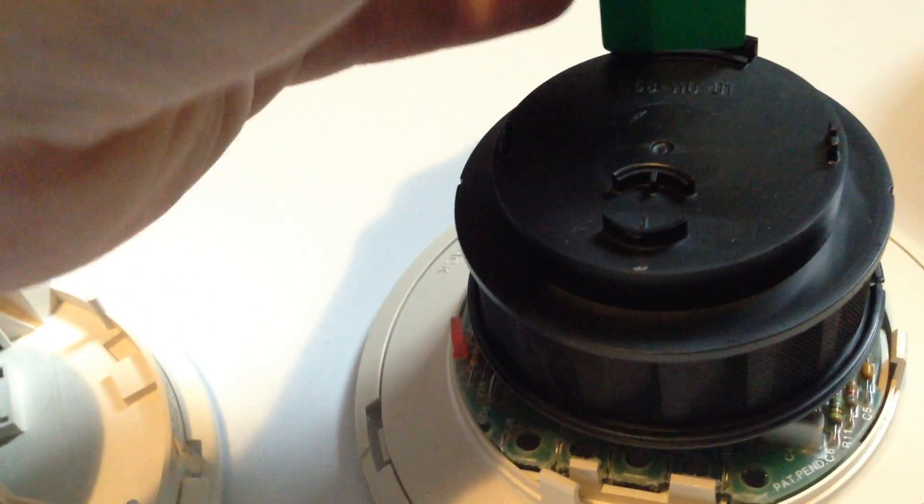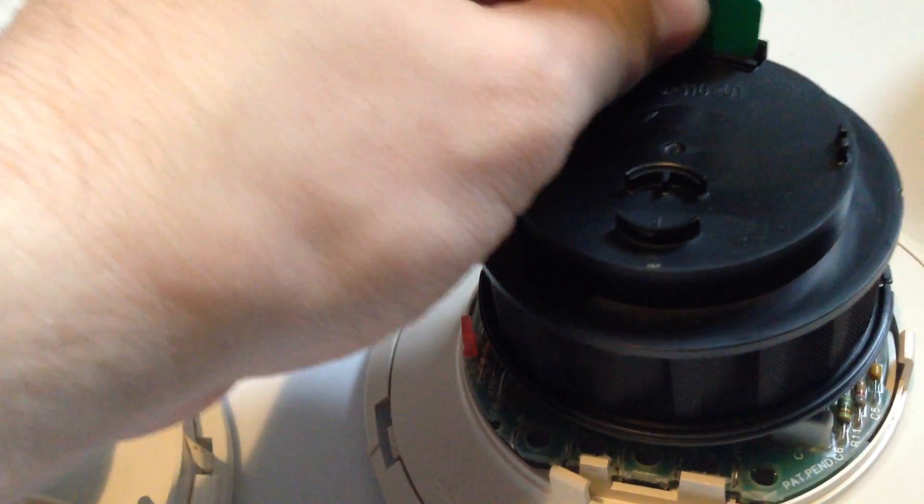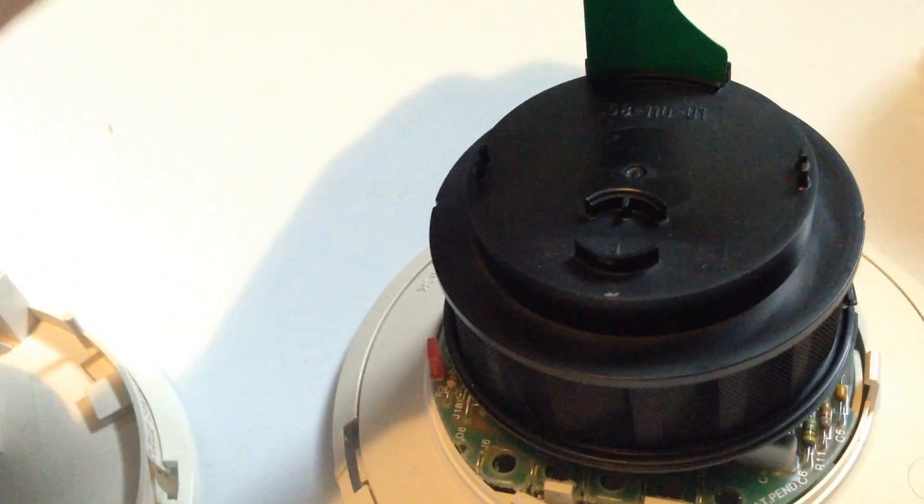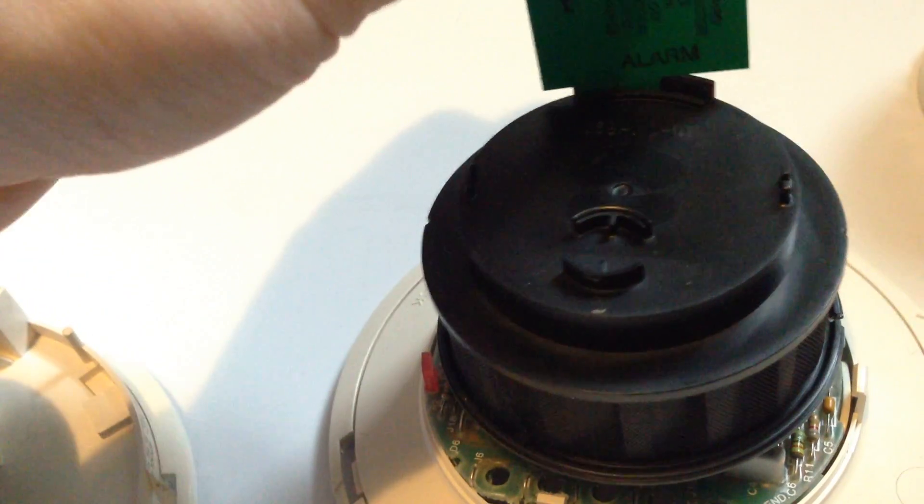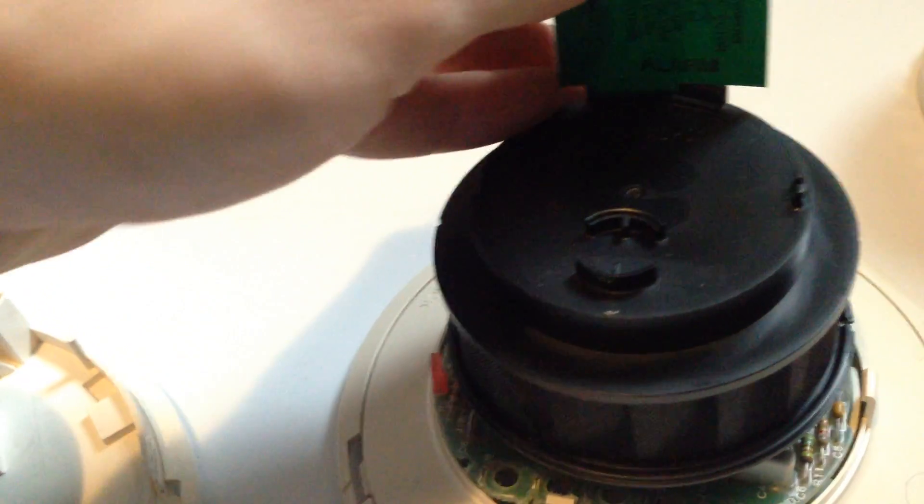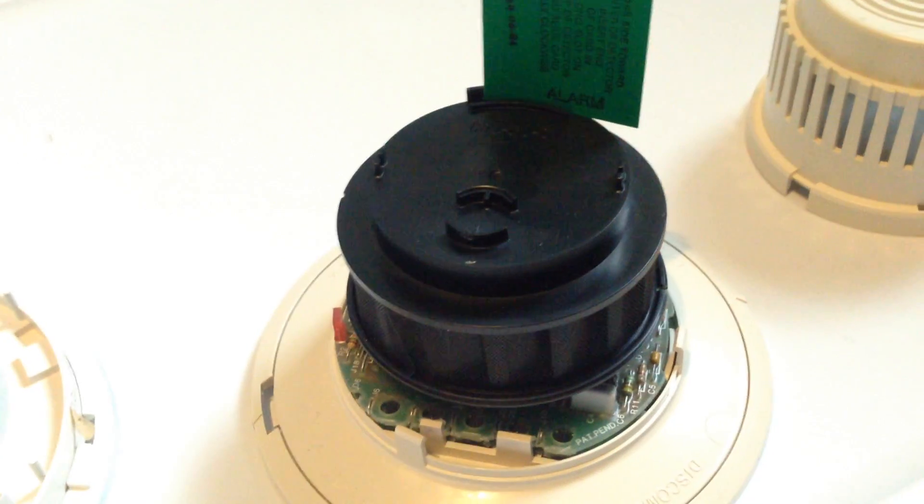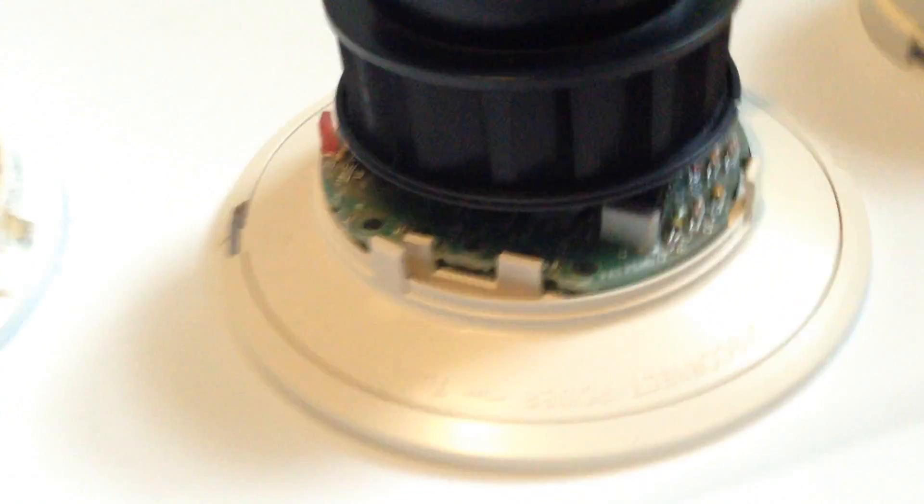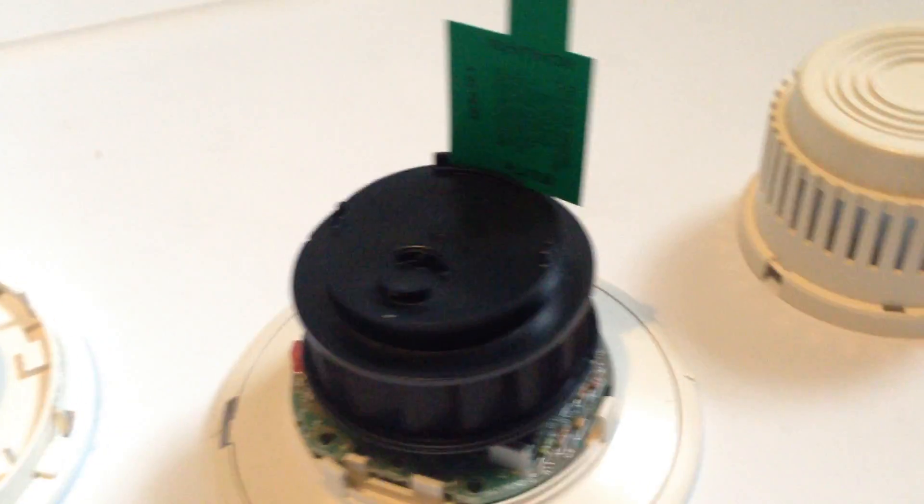Then, if you want to actually test it to put it into alarm, you put the larger side in, and then you slide it over, like this. That blocks the sensor temporarily, simulates an alarm, and that activates the detector.